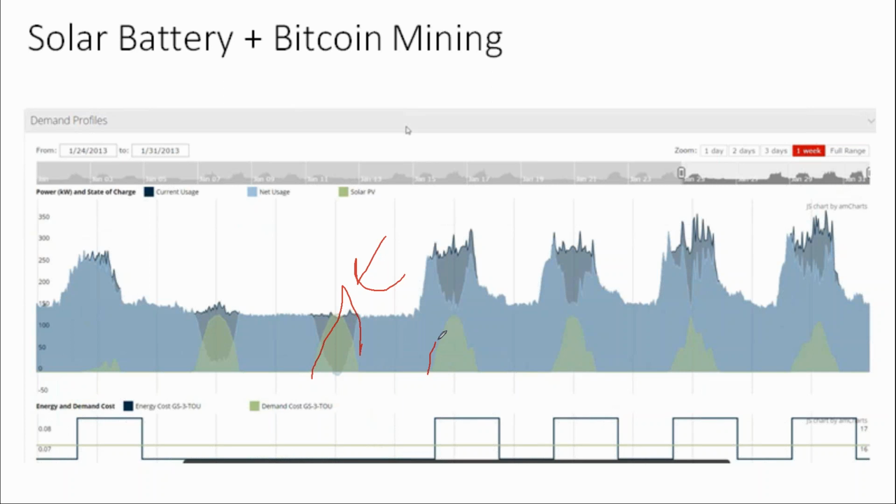So what we're doing with this solar array is sizing it to take their base load during their day, during their peak base load, and dragging it down to the night base load. So we're taking the sustained daytime load and making a solar array large enough to get it down to the nighttime base load. And I would even do it maybe a little bit more than that, because solar is relatively cheap nowadays.